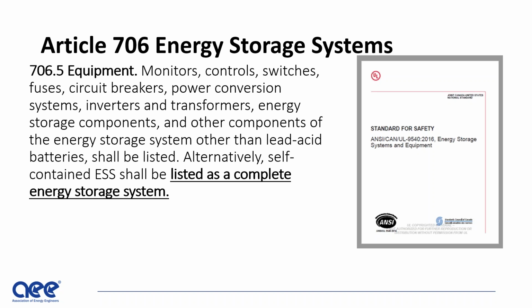Utilities, you'll see it at grid level, for maintaining voltage stabilization in areas where you get a swell or a voltage drop. Sometimes they'll use capacitors for that, but we've seen some areas, with wind or PV or even not at all, where they use energy storage as a voltage stabilizer, which is what the APS was doing.